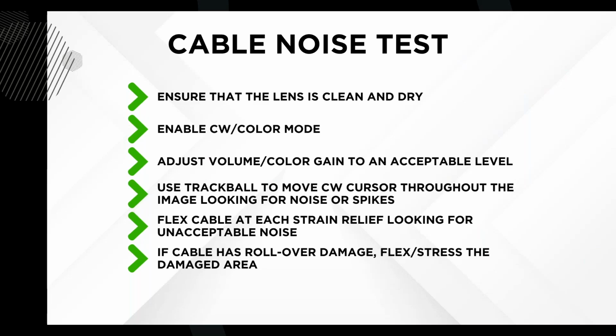So I'd check it in color, and then I'd also check it in Doppler. This is pulse Doppler, so you probably won't see it as much, but check it here as well. If I saw any color spikes that look like that in that area, that would indicate some defect in the cable or in the transducer. This particular one, I don't see any color noise with it.